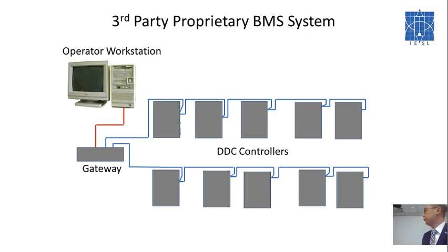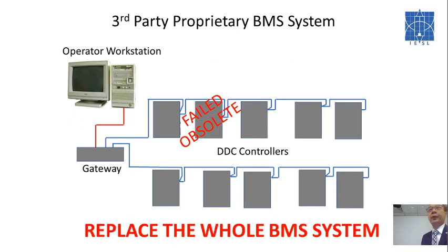First option: if today one of the controllers fails, you will request a quote from the BMS contractor. If it's obsolete, the contractor will say sorry, I can't provide you with a quotation. So what can the owner do? The owner only has one choice now, to replace the whole BMS system. Worldwide, everybody will face the same issue with this.